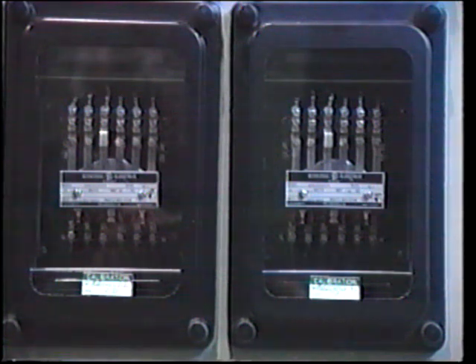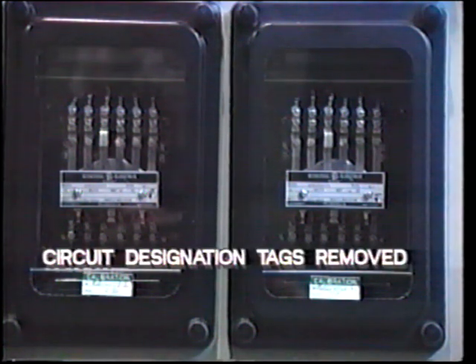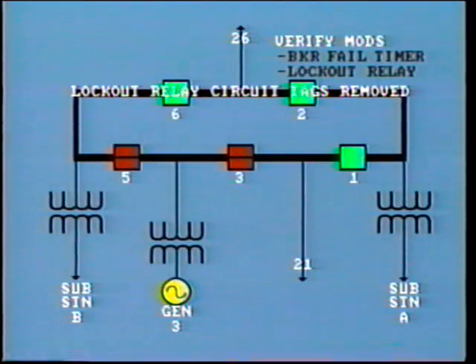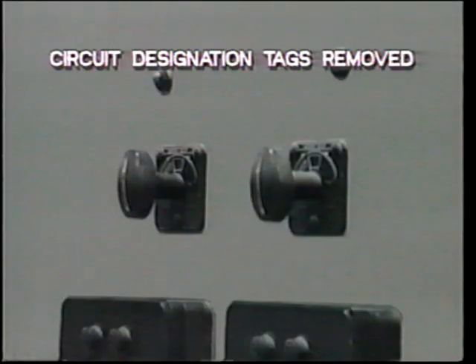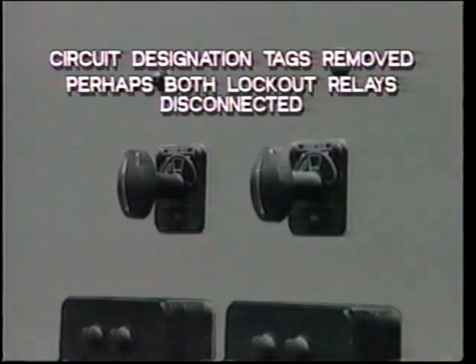However, when they went to the relay panel, they found that all of the relay circuit designation tags had been removed. This included the 2 lockout relays, one associated with the breaker 2 failure and the other with breaker 6 failure. So the question arose, which one of these 2 lockout relays should they operate? Because the circuit tags had been removed, the technicians began to think that both lockout relays had been disconnected. After all, this was the eventual plan. Moreover, standard practice in this company was to remove circuit tags from disconnected circuits.